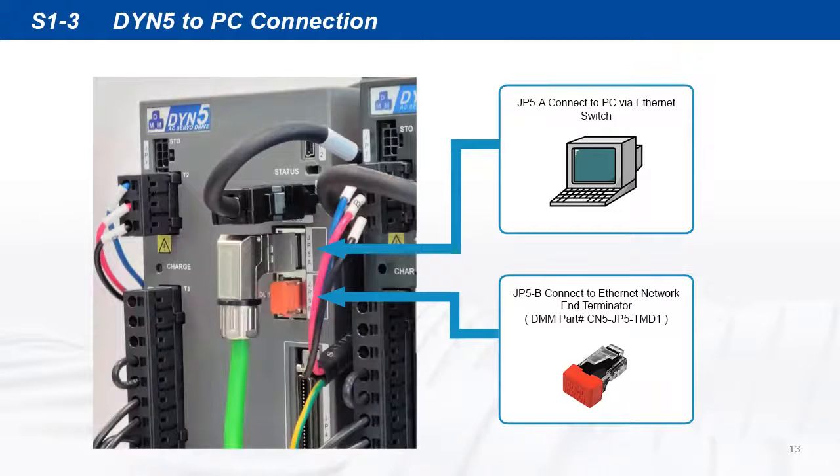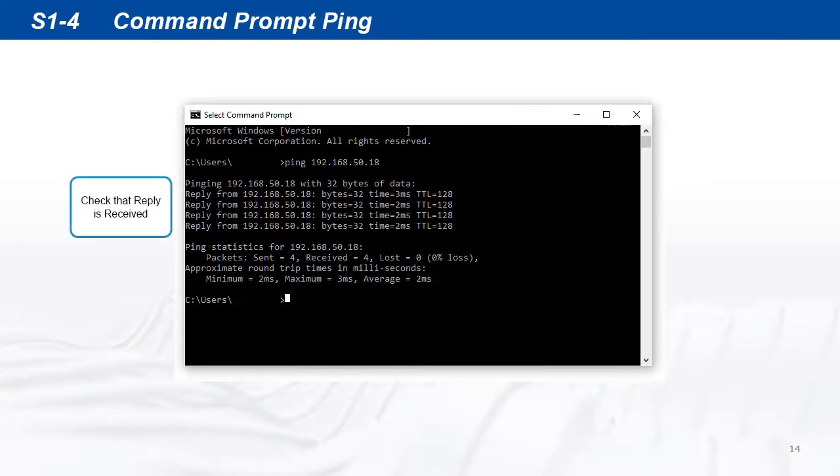Check that the Ethernet switch is powered on, and that the Ethernet network end terminator is connected to the last servo drive on the Ethernet daisy chain. Open command prompt and ping both servo drive IP addresses and check that replies are received from both drives. This confirms both drives are correctly in Ethernet mode.